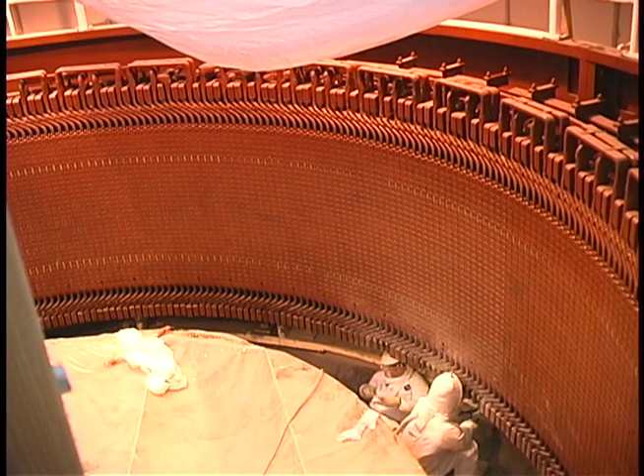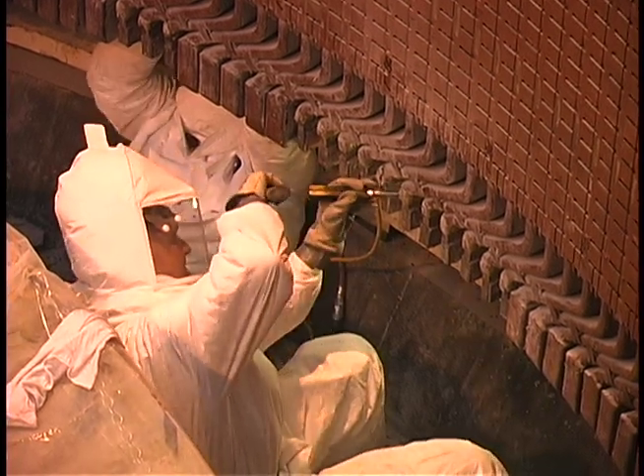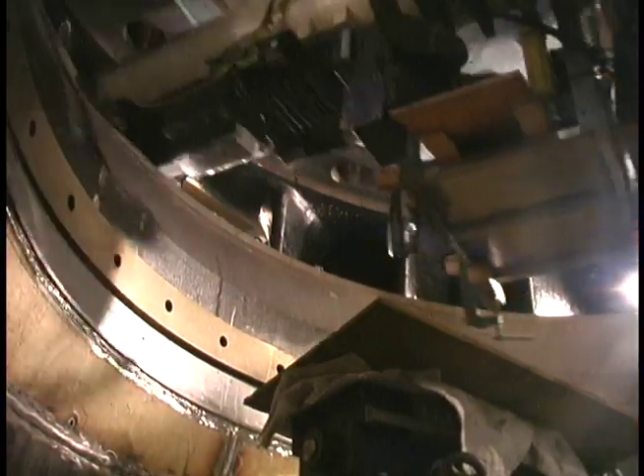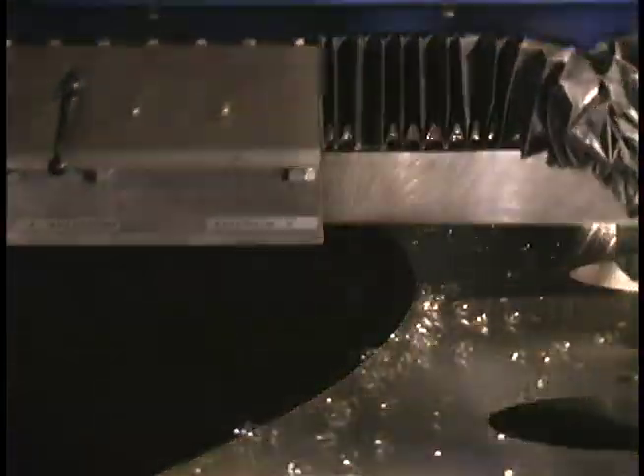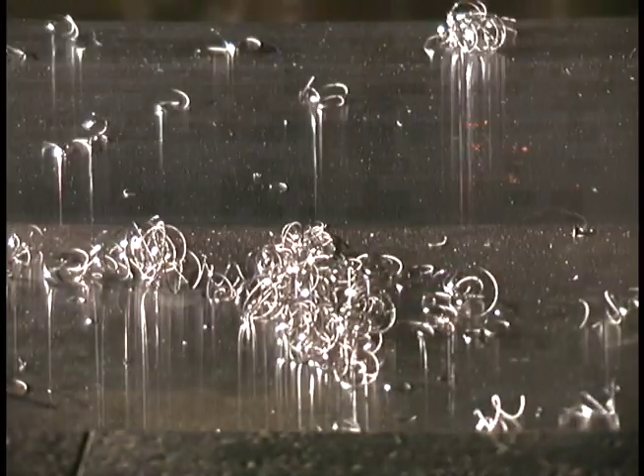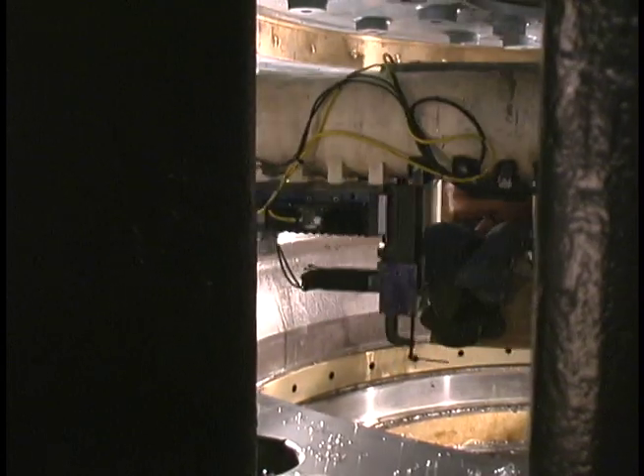Doing the work is both technical and time-consuming. Some workers even have to wear moon suits with an independent air supply to do the modern upgrades. There's another tool used here that also looks like something you'd see from astronaut training. Seattle City Light workers created it — it's actually called a boring bar, and that operation is used to machine the existing surfaces in the turbine area to accommodate some of the new parts going into Unit 24. The utility put the turbine overhaul out for bid, and Seattle City Light workers won the contract.